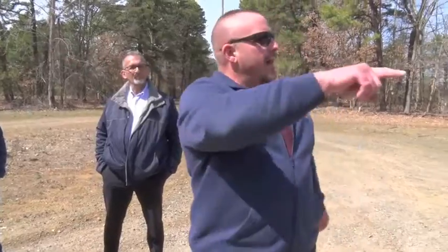This is called the Rainy Well. This is one of our bigger water producers as far as wells go. It's called the Rainy Well. It's a different type of design. This is a concrete caisson that goes down about 70 feet, and branching outward, there's 5 laterals, 12-inch pipes with screen that go out about 200 to 300 feet out. The reservoir around us recharges that groundwater that we pull from inside this building.